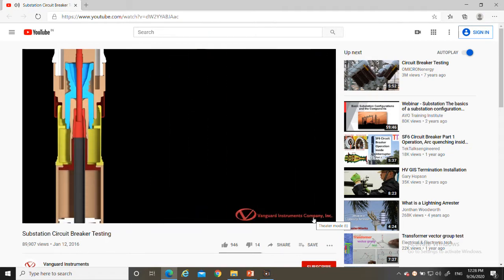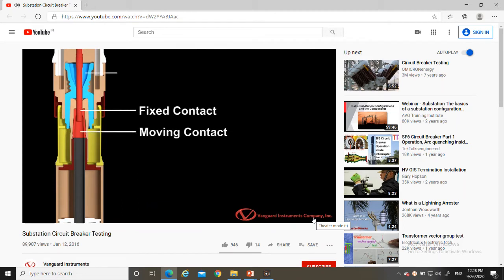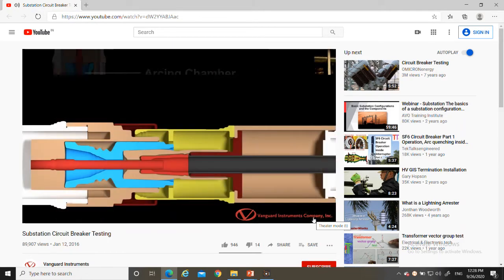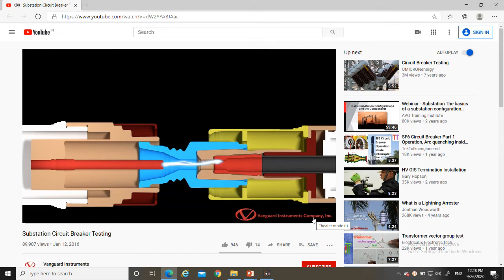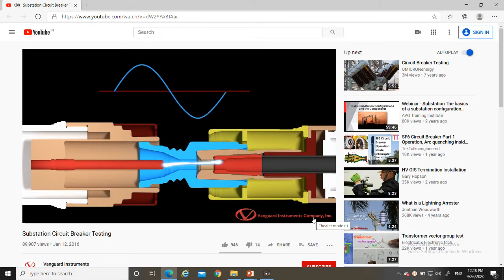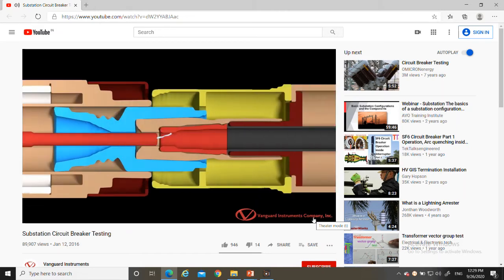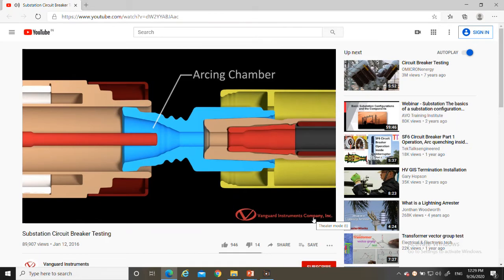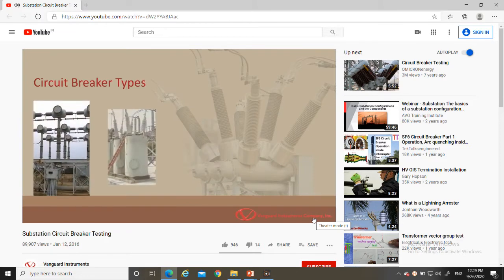Circuit breakers feature fixed and moving contacts housed in an arcing chamber, opened or closed by an operating mechanism. When the contacts open, an arc is created due to current interruption. An AC arc extinguishes at every zero current level but reignites immediately after crossing the zero point due to the voltage across the open contact. To avoid arc re-ignition, contacts must be separated with sufficient speed and the dielectric strength must withstand the transient voltage. Breakers are classified based on the insulating media used for arc suppression.